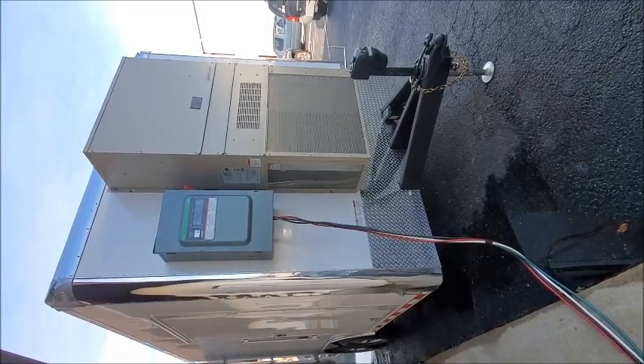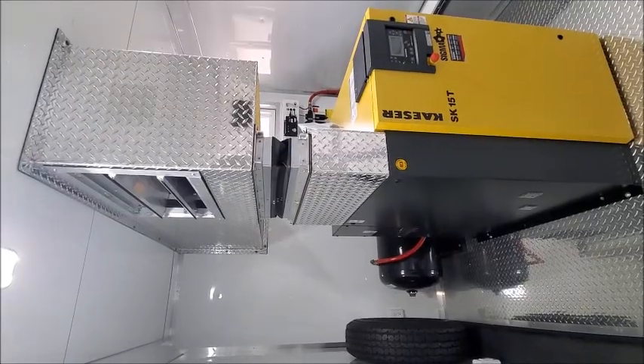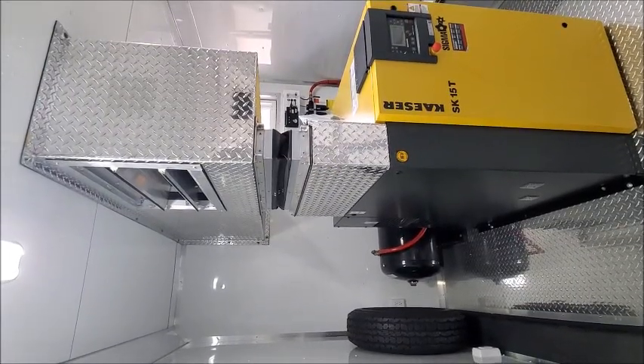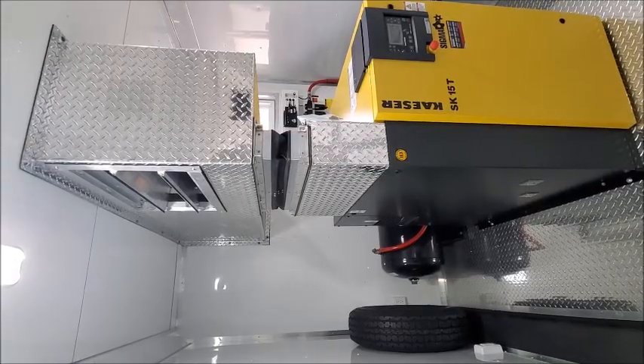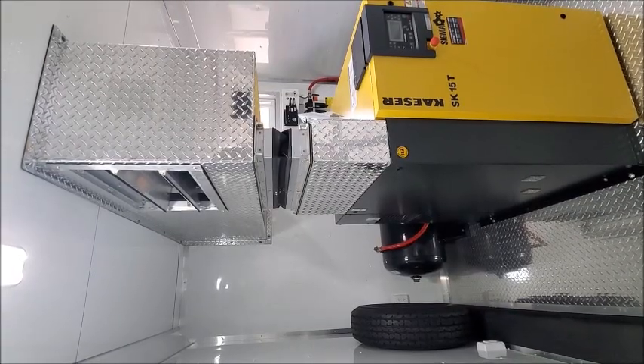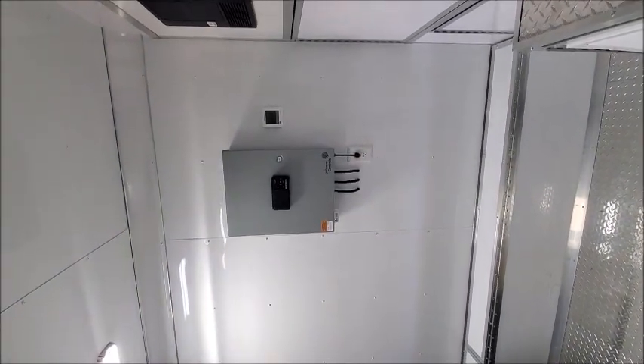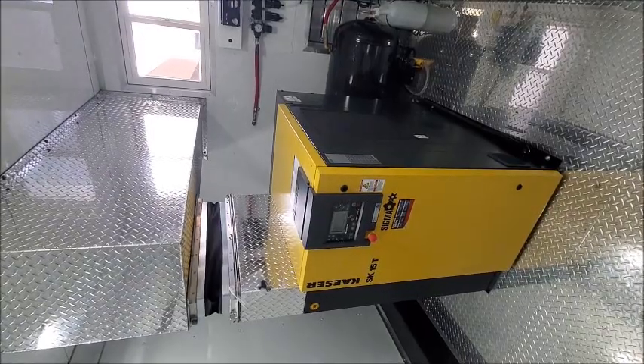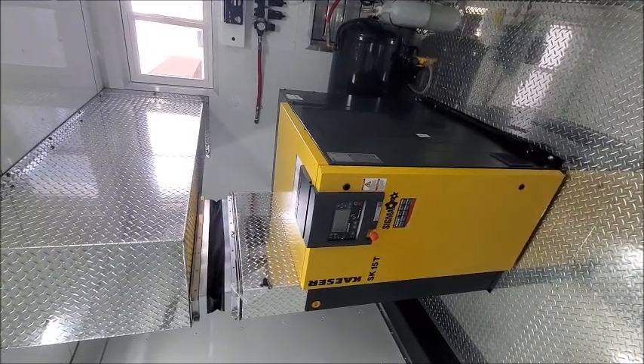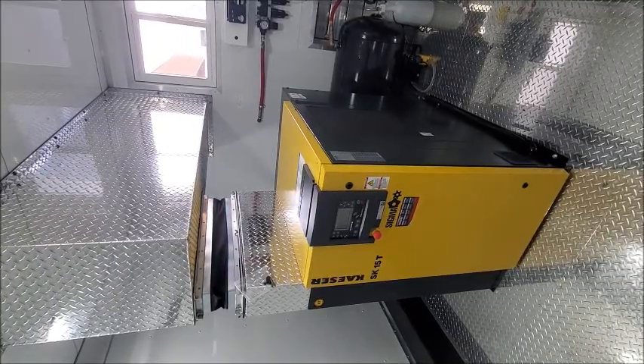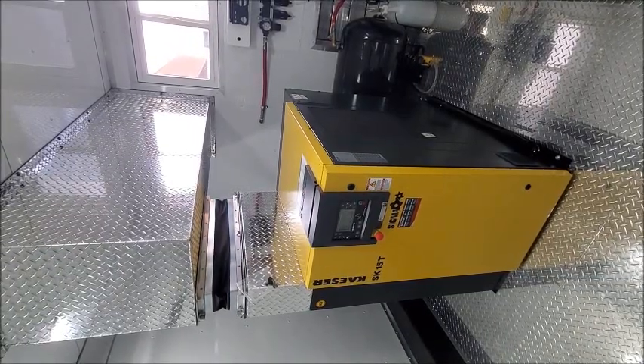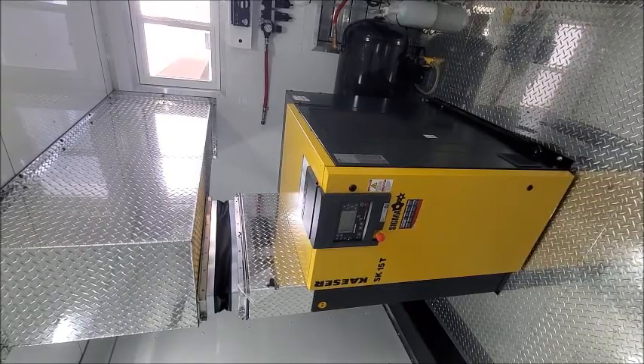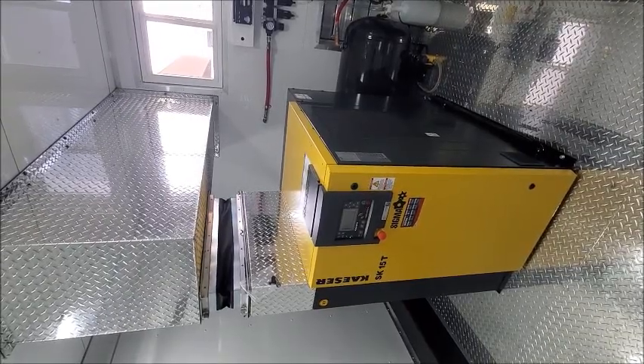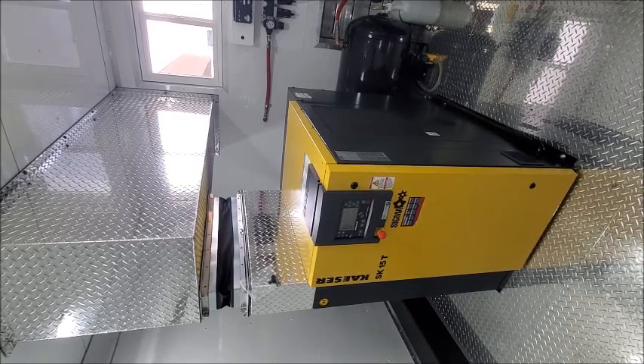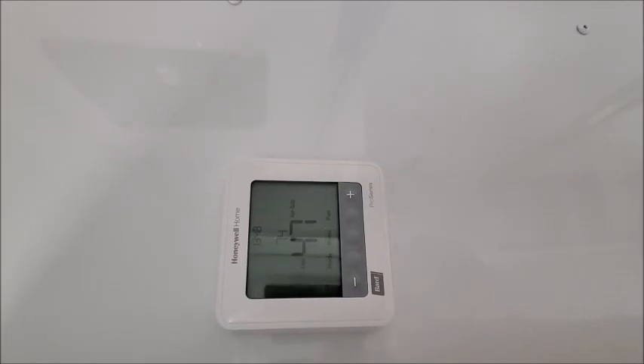output of 28,160 BTUs. The trailer's secondary heating source is an integrated heat recovery management system attached to the breathing air compressor and controlled by a central control unit. The breathing air compressor will be able to provide an additional 49,000 BTUs for heating needs. During compressor operation, the compressor should, under most circumstances, be able to provide all heating needs in the trailer, and the heat pump would be in standby as its thermostat will be satisfied.